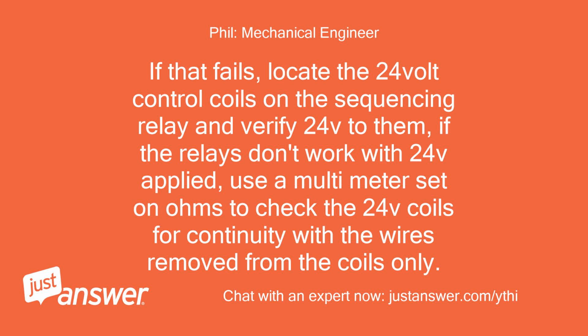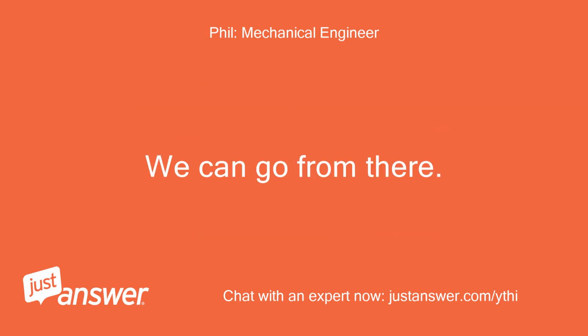If that fails, locate the 24-volt control coils on the sequencing relay and verify 24V to them. If the relays don't work with 24V applied, use a multimeter set on ohms to check the 24V coils for continuity with the wires removed from the coils only. We can go from there.